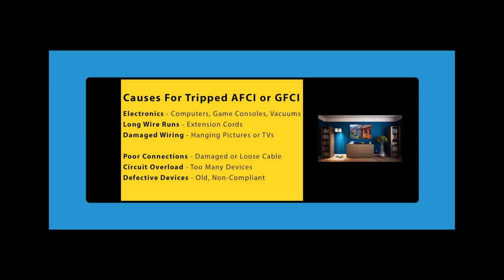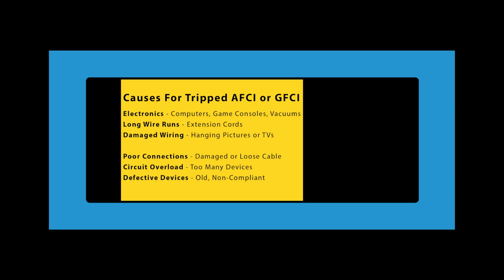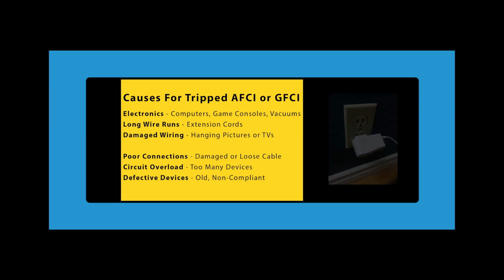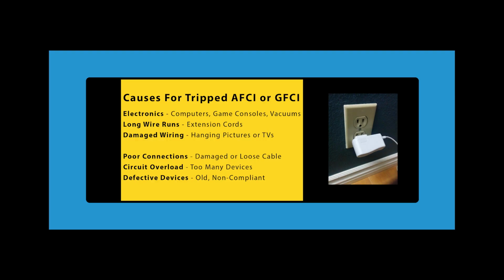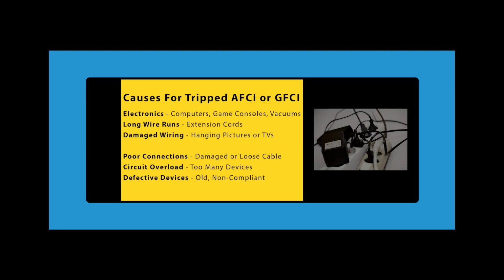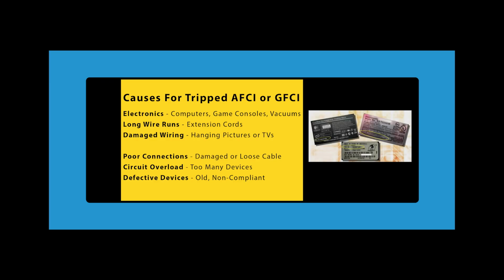Third, damaged wiring. This can happen as things are added to walls, such as hanging pictures or televisions. You can damage the wiring within the walls when driving screws or nails into them. Some other causes for a tripped AFCI could be poor connections, such as a device with a damaged or loosely plugged in cable, or circuit overloading, when too many devices are connected to a single circuit and they draw more current than the breaker is designed to handle. Also defective devices. Older non-FCC compliant devices or defective devices may generate actual arc faults inside of them, which can cause the AFCI to trip.